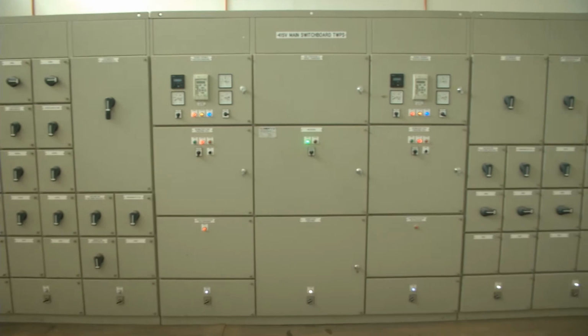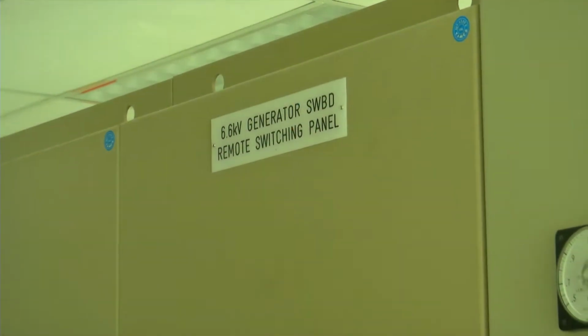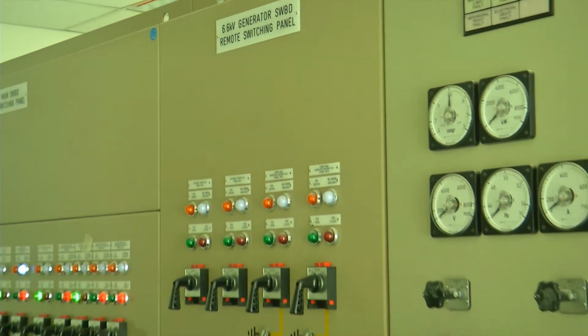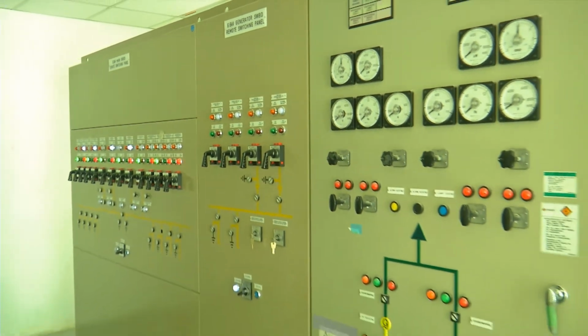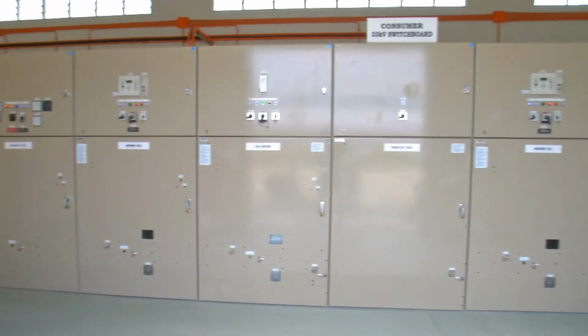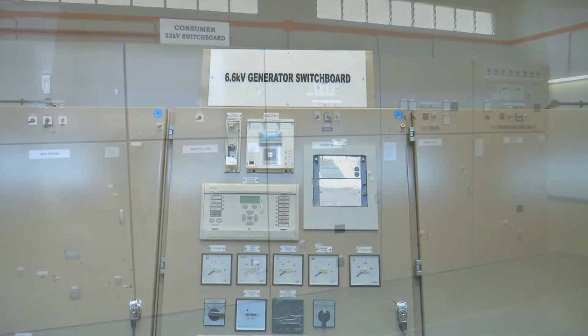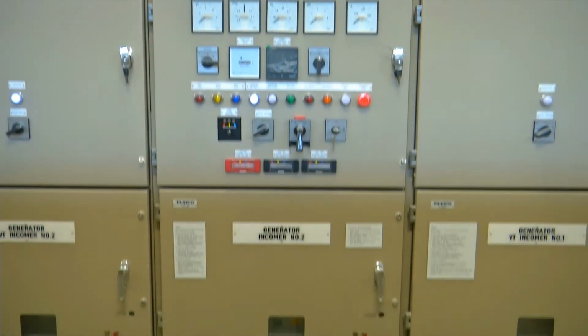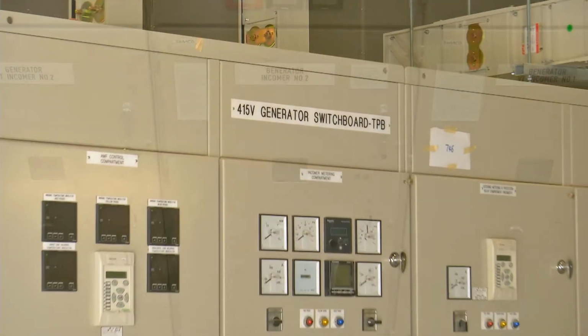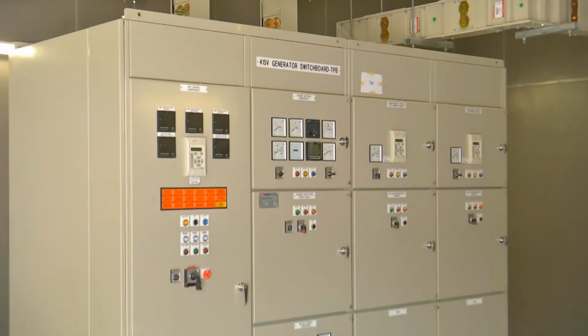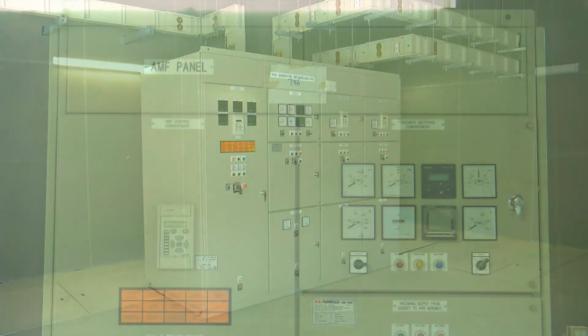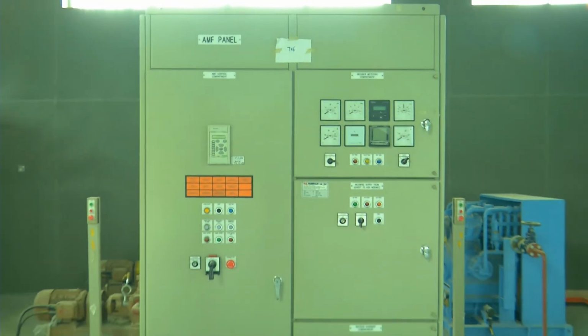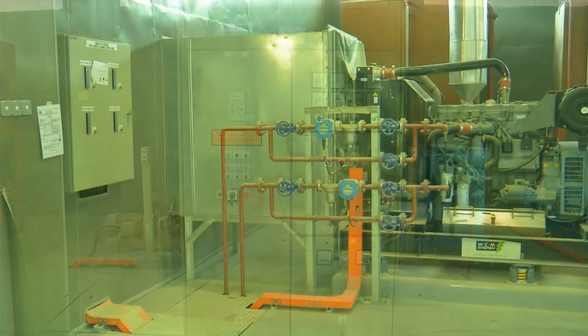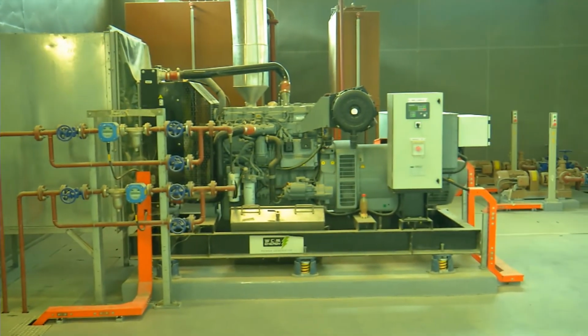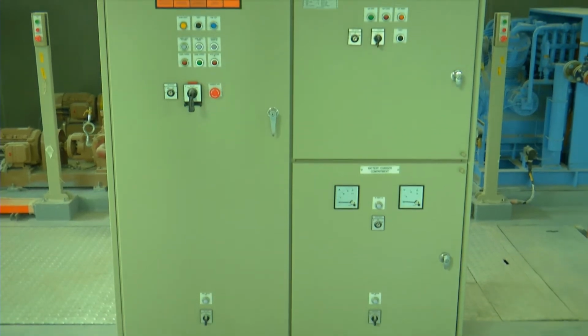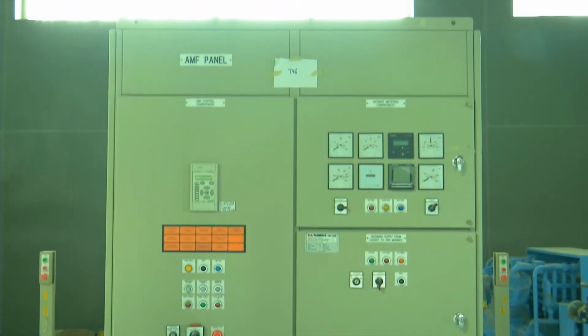Switchboard panels direct electricity from one or more sources of supply to several smaller regions of usage. It is an assembly of one or more panels, each of which contains switches that allow electricity to be redirected. Automatic mains failure, AMF, panels make the power switch to emergency standby generators, in the event of a significant loss of mains power or total blackout.